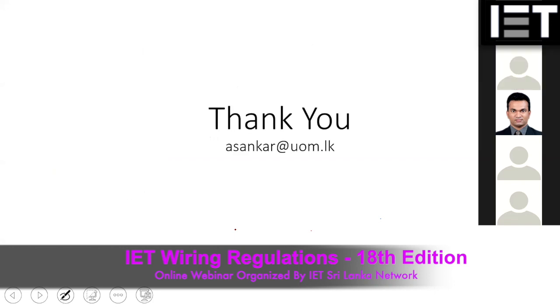So those are the major things which I detected as major changes in the regulation, as I said, because I have not covered everything in the regulation. These are the highlights of the changes compared to the previous version. Now you can see even this arc fault detection and SPD were not mandatory requirements in the previous versions. Those have now become mandatory requirements, and the risk evaluation and the earthing requirements have now become mandatory, so you have to adapt those things in the new design.